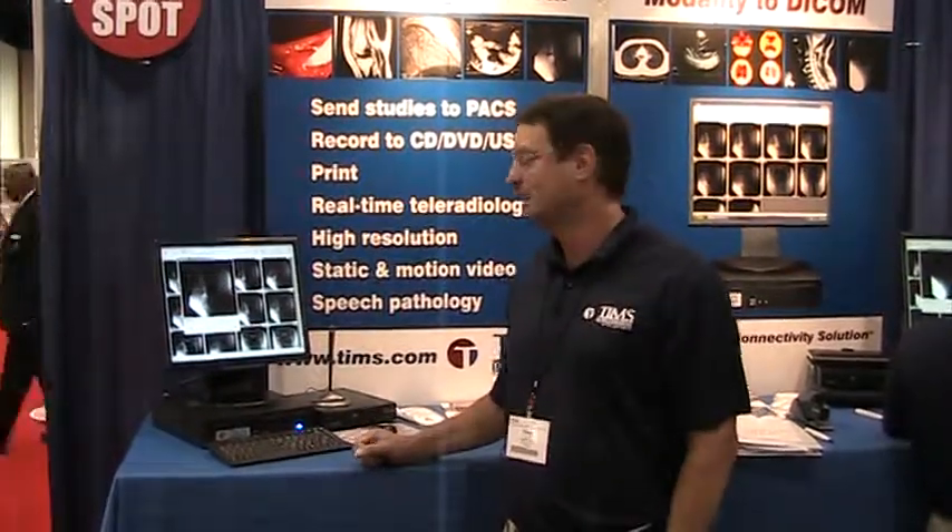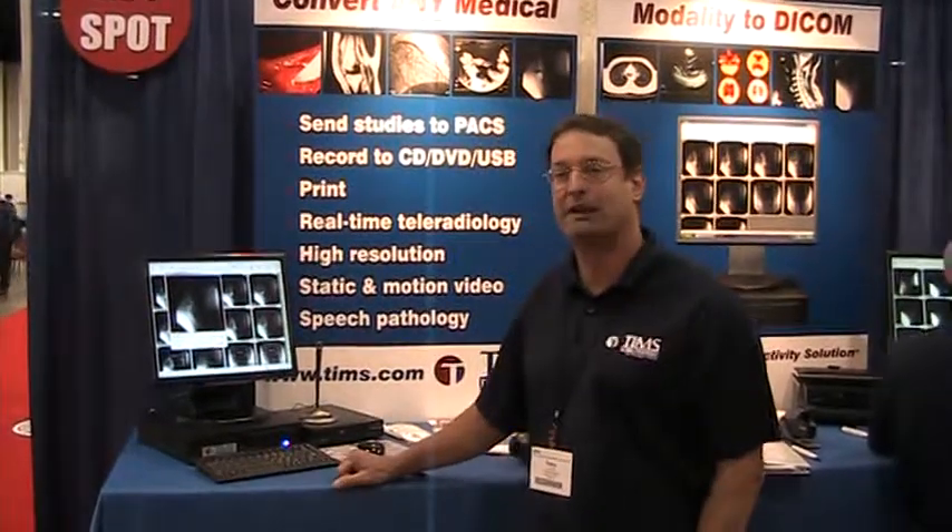With our TIMS DICOM system, we have a small footprint computer where we can convert any medical modality to DICOM. That includes ultrasounds, endoscopes, fluoro, cardiac cath lab, nuclear medicine — anything that has a video signal, we can convert that to DICOM and get it into your PACS system.